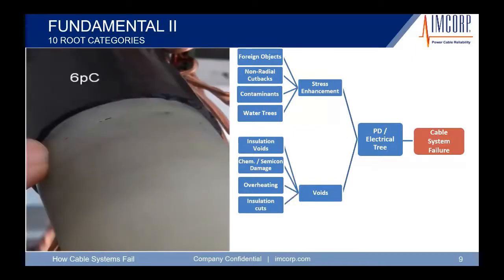Insulation cuts. This is probably one of the more popular issues that we see out in the field. The guy makes a good ring cut, but his blade goes a little bit too far into the insulation. In this area where we see a lot of electrical activity, that's where we first disrupt the electrical field. That high concentration of activity will begin to break down that insulation in a lot faster fashion.